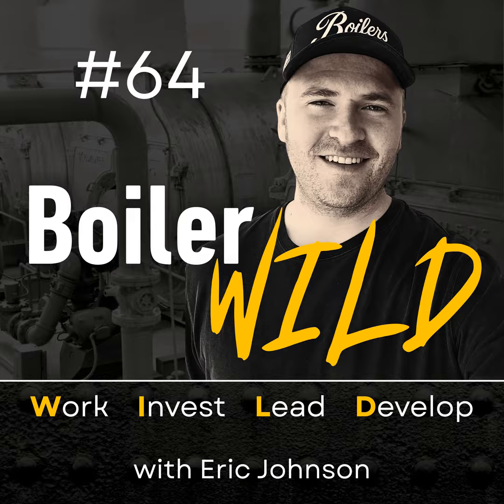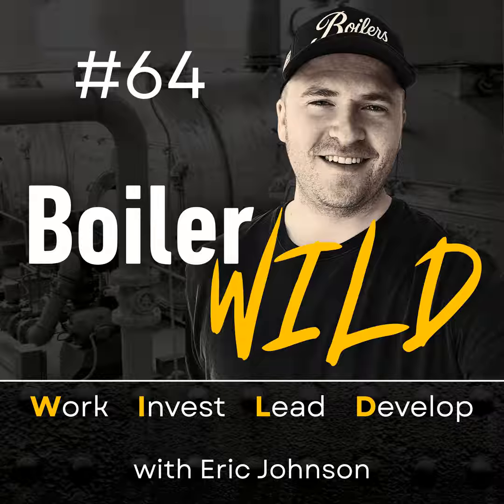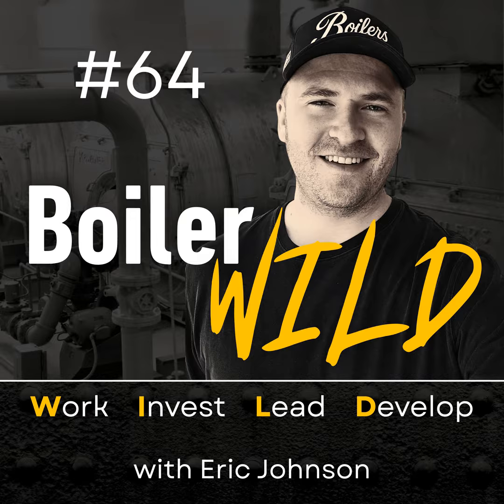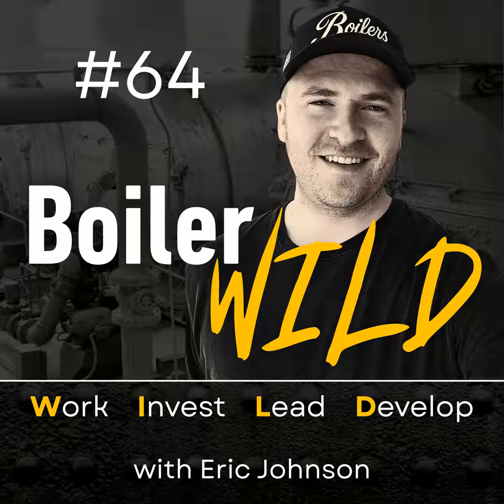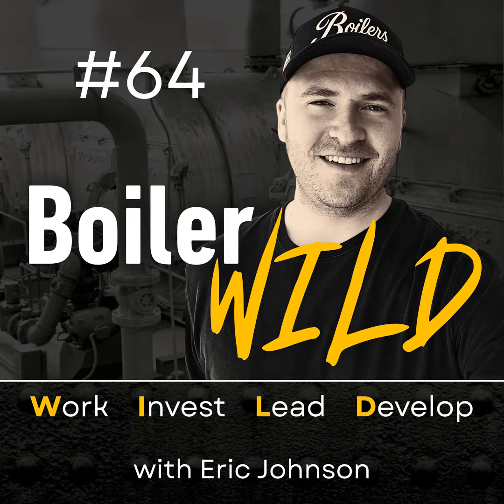recycling limit terminal. And if any of those switches that I mentioned open, that series circuit is going to stop the voltage from hitting that terminal on the Honeywell 7800 or any other controller that you have. It doesn't matter. I'm just using the Honeywell 7800 because it's typically the most common one people see. It will stop the voltage from hitting the input terminal of the Honeywell 7800 for the recycling limit, and it will tell the Honeywell 7800 to go into post purge and then to shut down the boiler/burner.